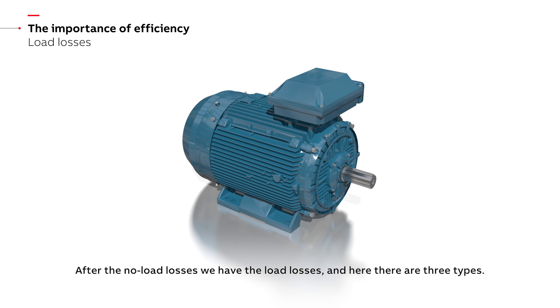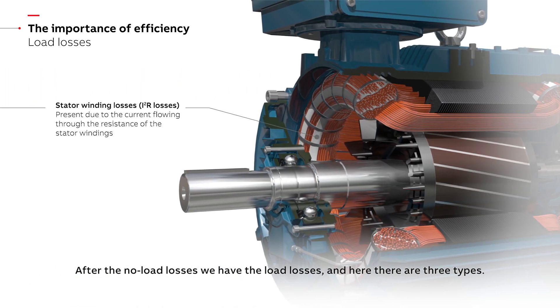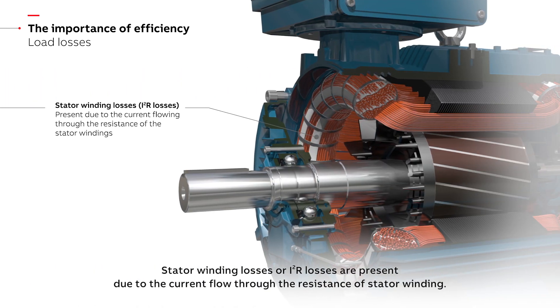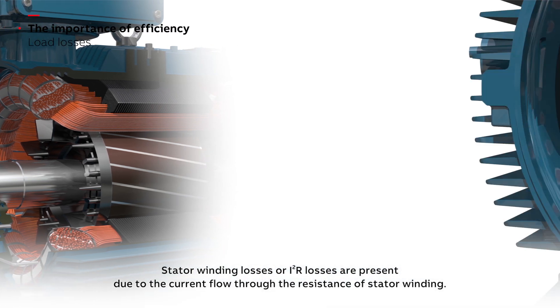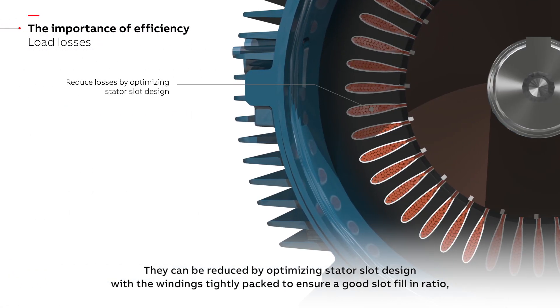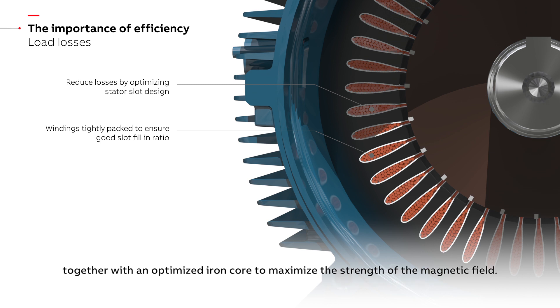After the no-load losses, we have the load losses, and here there are three types. Stator winding losses, or I squared R losses, are present due to the current flow through the resistance of the stator winding. They can be reduced by optimizing stator slot design with the windings tightly packed to ensure a good slot fill ratio, together with an optimized iron core to maximize the strength of the magnetic field.